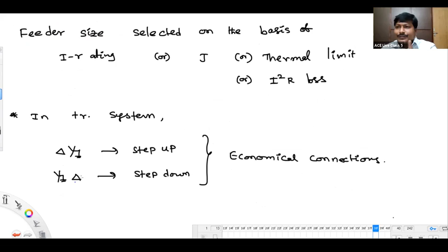Step down. Definitely in the distribution system, the lower side of the system, whatever transformers we have are step down only. According to the economical view, what connection should we use for step down? We have to go for star grounded delta. But as a special case, in the distribution system, we always go with a delta star ground transformer. All the time, we should go for a delta star ground transformer.